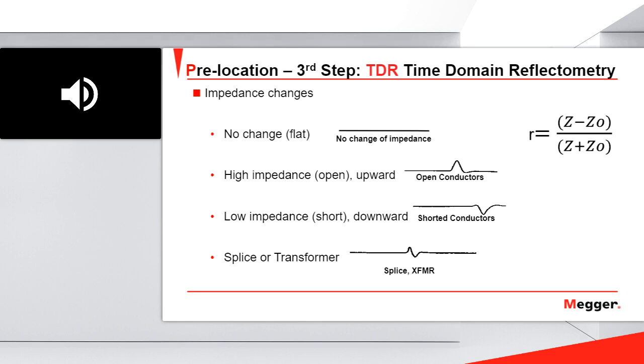Before we explain this, I would like to talk very quickly about how a change of impedance looks. For instance, if I don't have any change of impedance in my cable, I will see a flat line. If I am seeing the end of my cable, or the conductor is cut, or the concentric is cut, I will see an upward blip. If I see a short, for instance, between the conductor and the concentric, I will see a downward blip, like this one. And if we have joints or transformers connected to the cable, I will see a change of impedance like this one: first an upward and then a downward blip. Okay, so this is what a change of impedance looks like in the TDR.